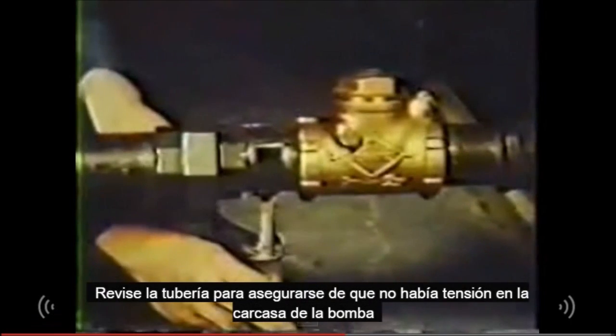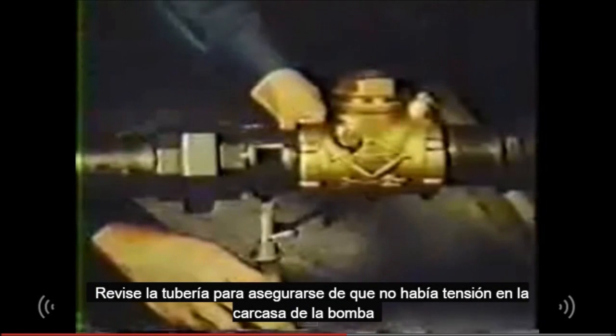Check piping to be sure there is no strain on the pump casing. Rotate the pump shaft to be sure it turns freely. Jog the motor to be sure it is turning in the right direction. Check any safety relief valve to be sure it is installed correctly.